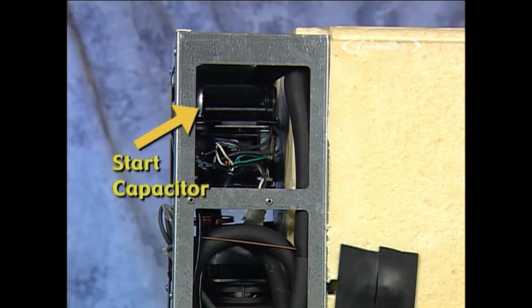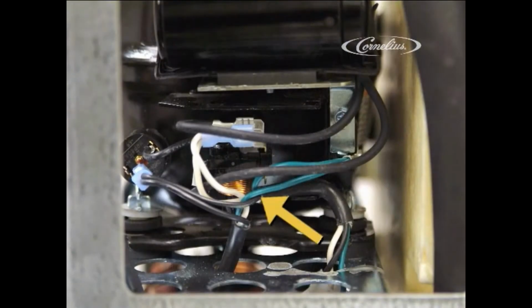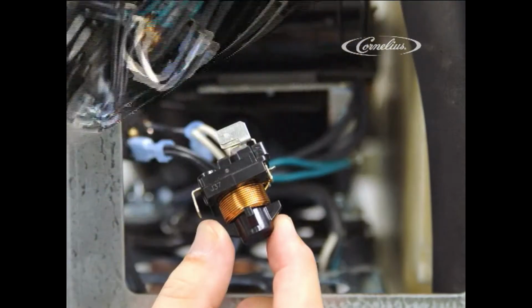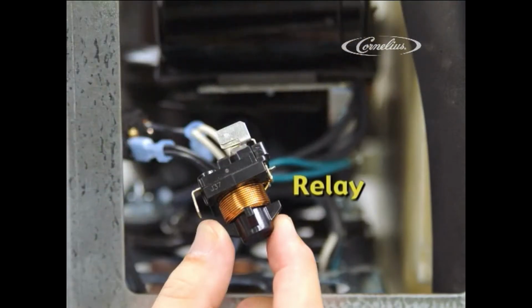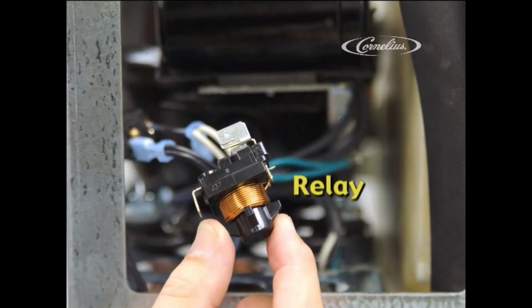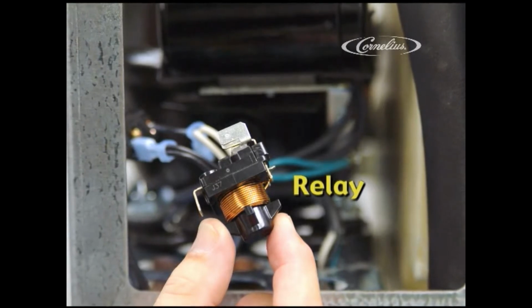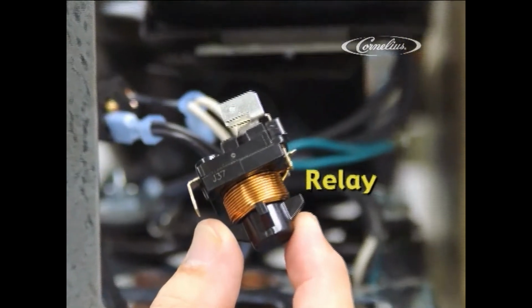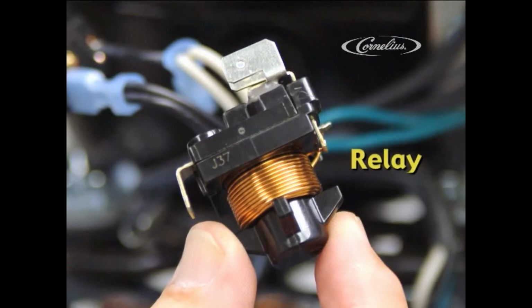It is wired in series with the start winding and, by discharging, helps to increase the compressor motor's starting torque. This is a current magnetic relay. It works much like a solenoid valve. A spring holds the relay open when the system is idle. When the control device, in this case the IBC, closes and sends line voltage into the compressor, the relay becomes magnetized and closes the contacts. This action energizes the start winding circuit and the motor inside the compressor starts. As the motor speed picks up, the amperage draw decreases, thus reducing the magnetic field in the relay coil, and the spring then opens the contacts, de-energizing the winding circuit.